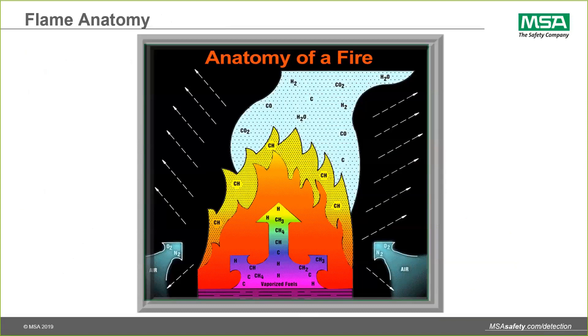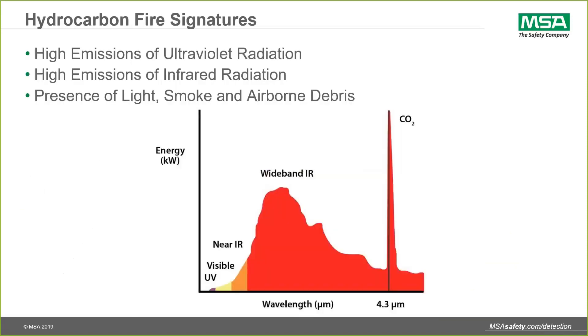If you look at that signature on the next slide, the hydrocarbons — as you look at energy as a function of light wavelength across the bottom — you'll see the emissions. You'll have some ultraviolet, some mid-infrared, and also some light, some smoke, some airborne soot and debris. But one characteristic very common to hydrocarbon fires is this CO2 emission peak centered on the 4.3 micron light wavelength. That is a consistent signature of all hydrocarbons, ranging from solid materials to liquid materials, and that is a frequency of light that most manufacturers of optical flame detectors are very interested in measuring.